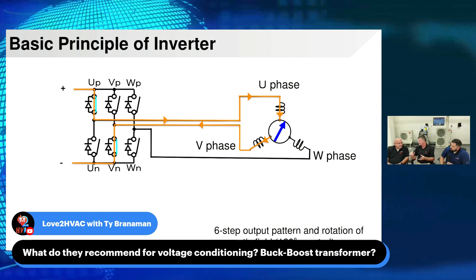So what do we recommend for voltage? What range is good on our incoming voltage? I know we typically have a window range, but if we're experiencing high incoming voltage, what would be a good solution? Well, the equipment is typically rated at 208, 230, plus or minus 10%, so that's about 187 to 253 as the range. If you're experiencing higher voltage than that, I recommend a buck boost transformer.